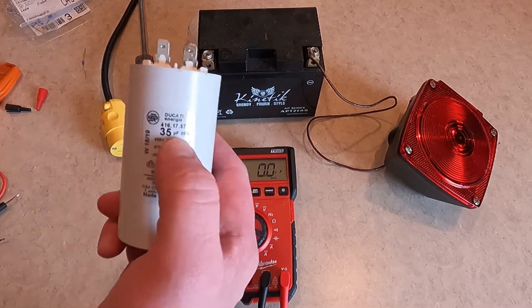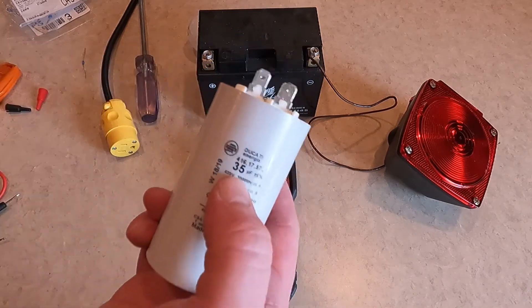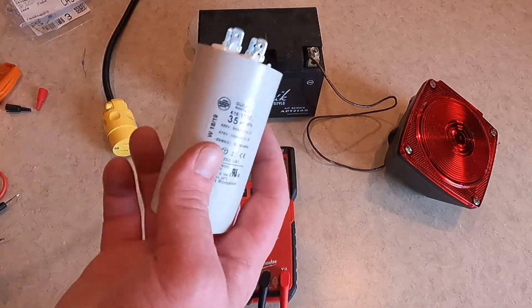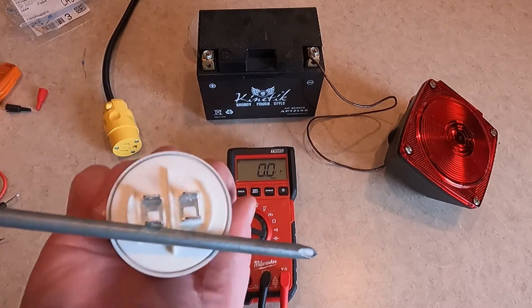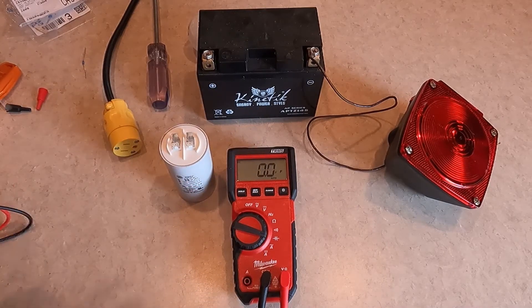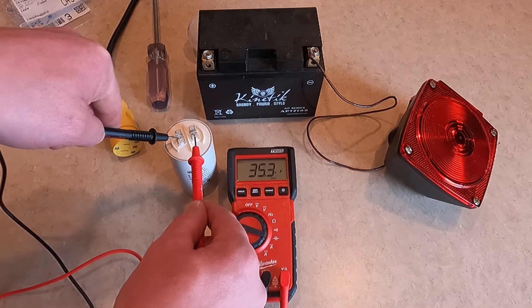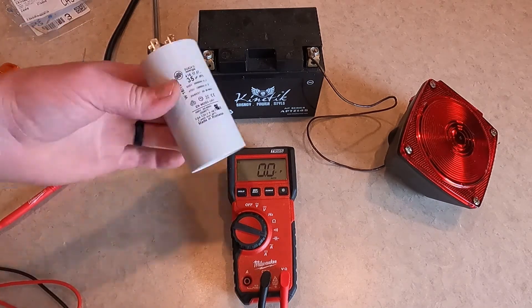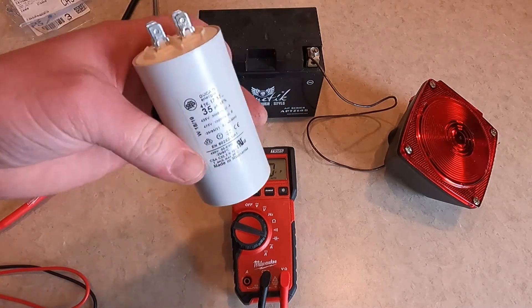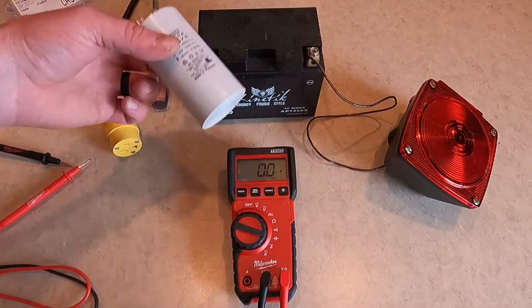The unit of measurement is µF — microfarad. This one is rated at 35 µF, plus or minus 5%. First, we're going to discharge it by bridging between the two legs so we don't shock ourselves. It reads 35.3 µF, so we know this is a good capacitor — it's within spec. As I mentioned, capacitors are the most common point of failure in electric motors and capacitor-type generators; they're cheap parts and very easy to check.